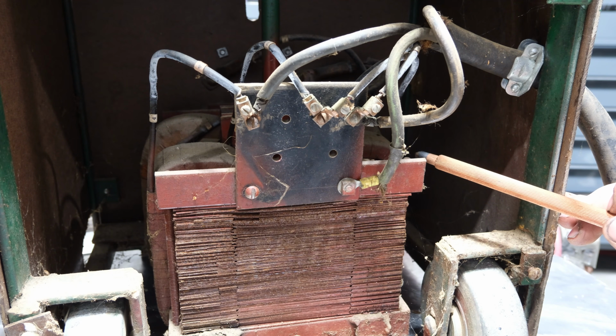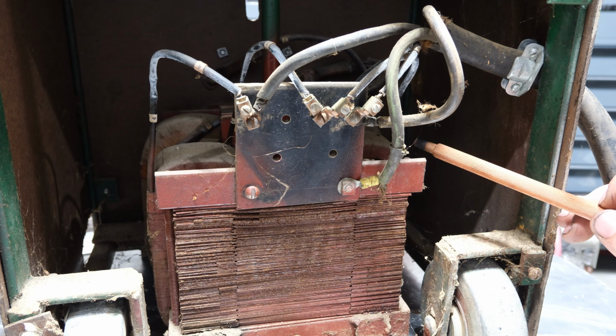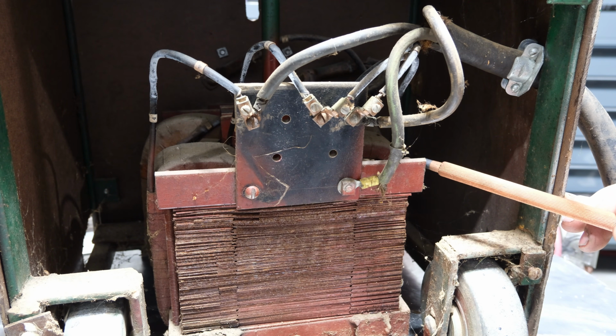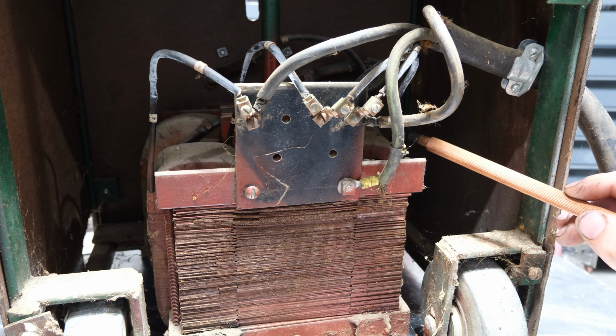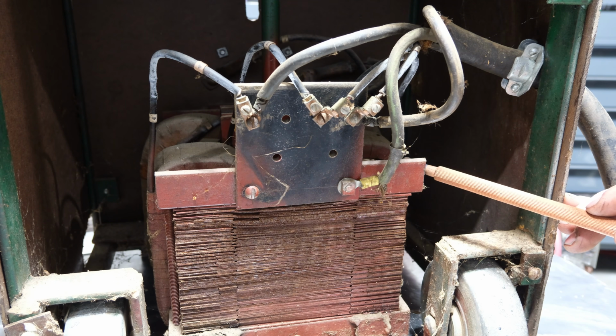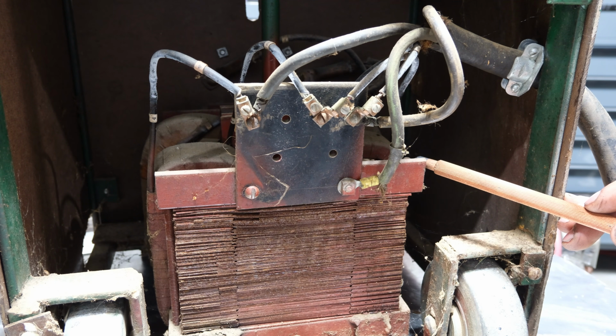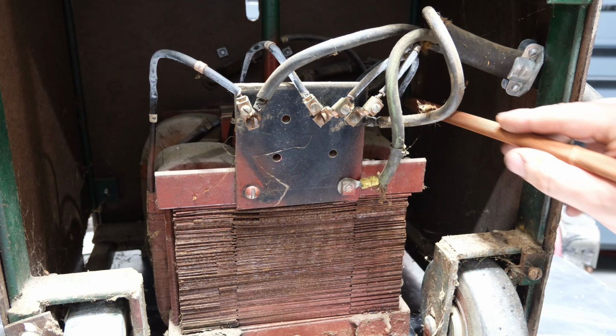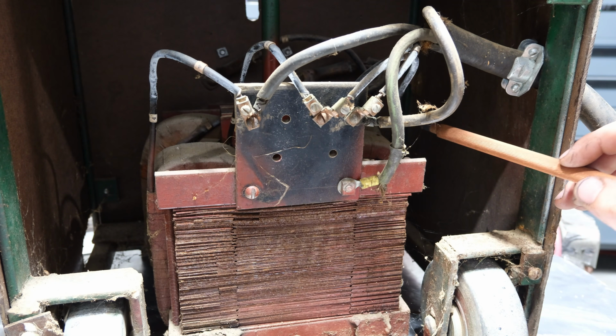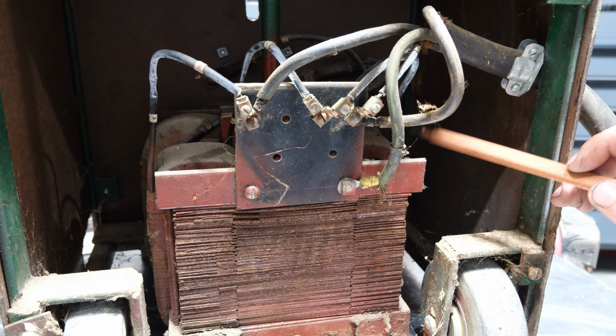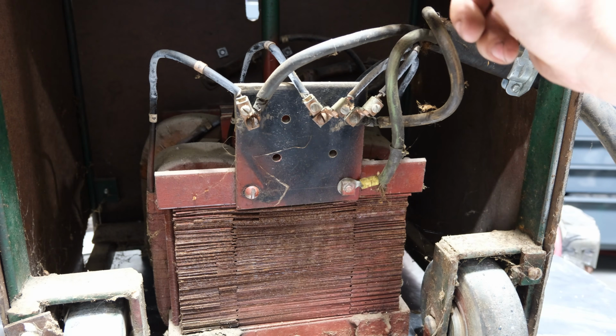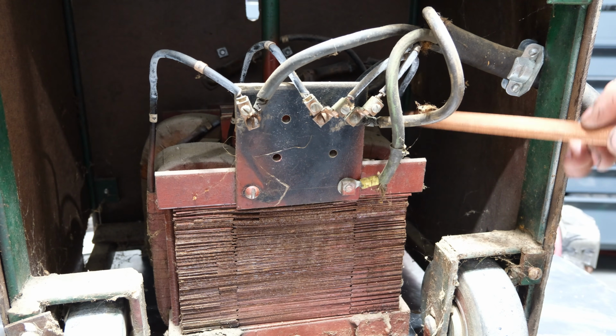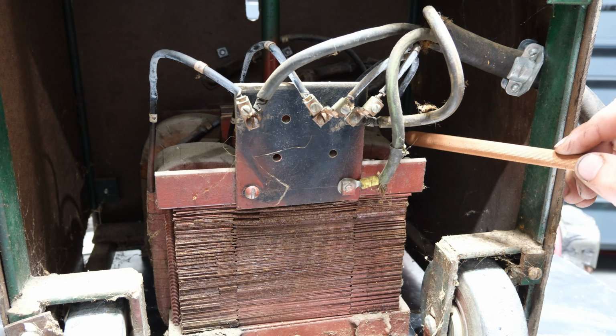This is not a transformer out of a tombstone. This is an absolute gigantic transformer that I don't think would be in anything less than a 250 amp class, if not bigger, welder. Which is kind of odd that that would be in this size of machine. You can see this doesn't actually take up more than about half of the case. The rest is dead space, more or less, for that amperage indicator up here. But this is realistically, even for the day this was probably built, way oversized for a 200 amp welder.